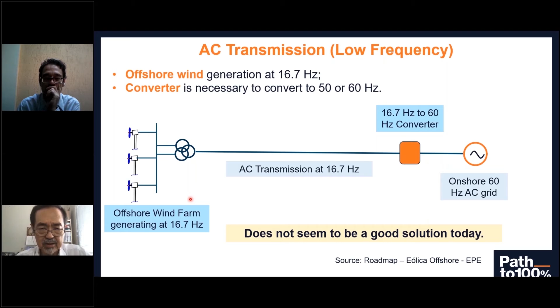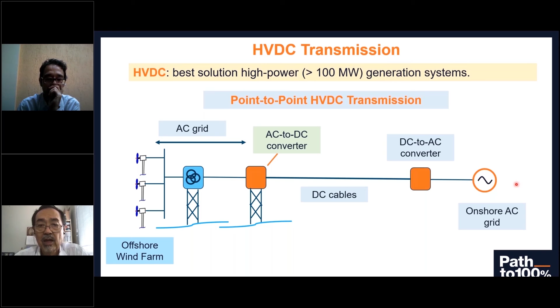Basically, if the power is above 100 megawatts and you have 50 or more kilometers from the generation to the connection point, you have an AC grid close to the wind farm. You need an AC to DC converter, DC cables, and then you have to convert again from DC to AC and connect to the grid.